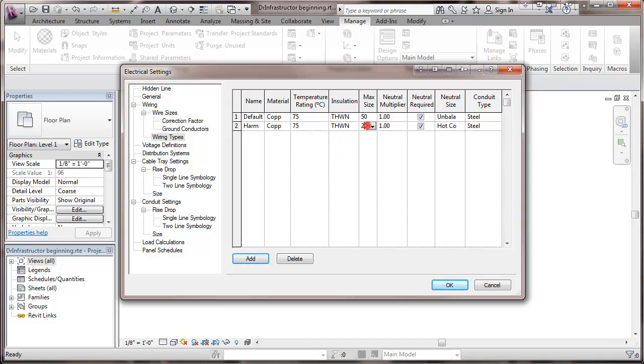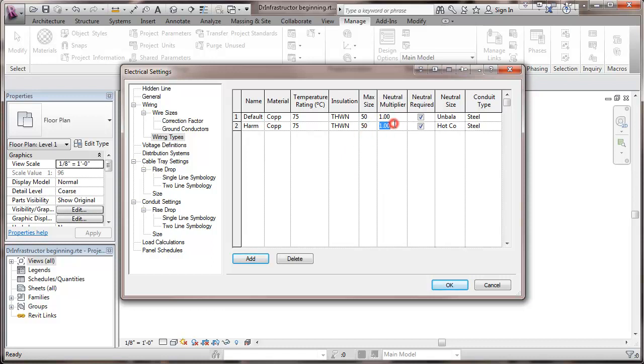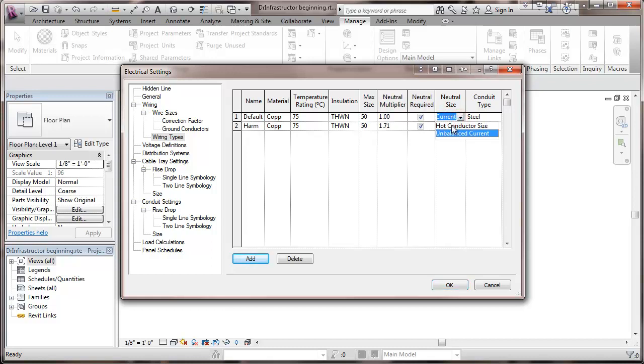Again, that maximum size. Here, however, on my neutral multiplier, I'm going to go with 1.71. I'm going to oversize the neutral in this case. Neutral required. It's being sized by the hot conductor. And it's also being steel conduit. I'm noticing here my neutral size. I want that sized by my hot conductor size too.